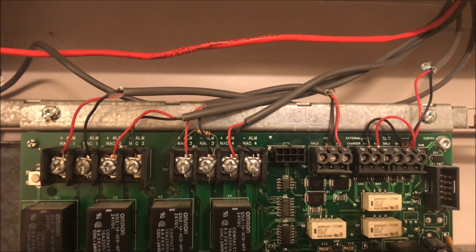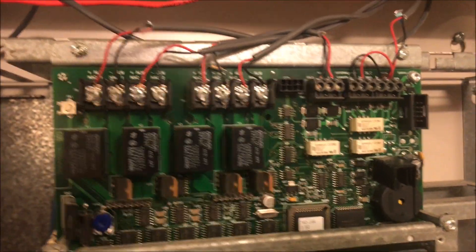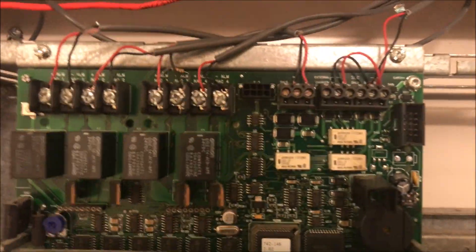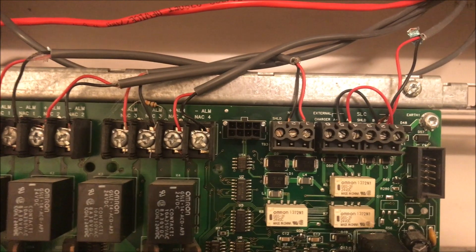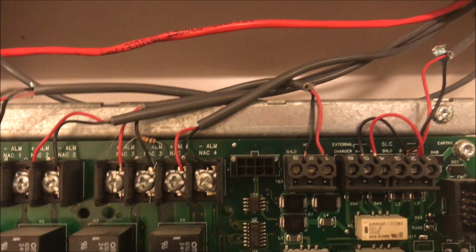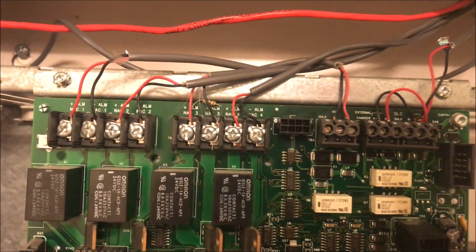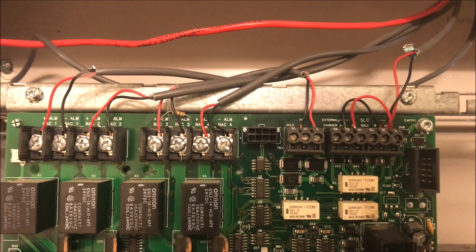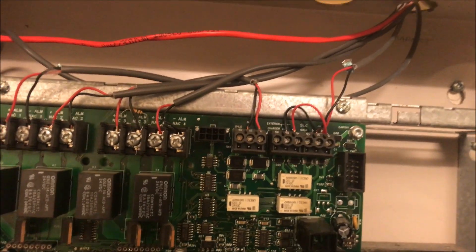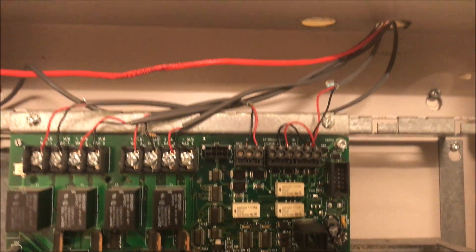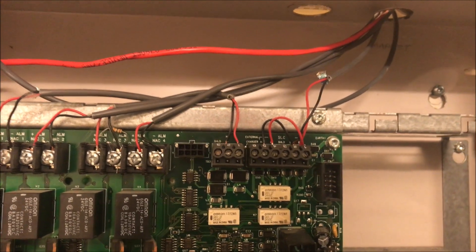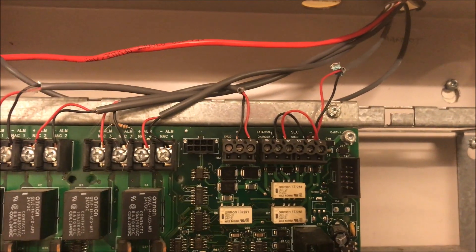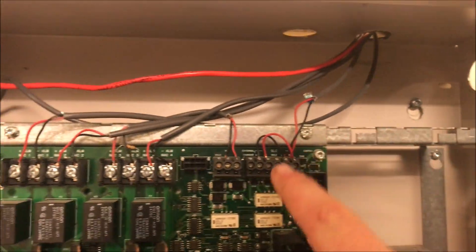Next, this is your IDnet channel. You can have this set up as Class A or Class B. I have mine set up as Class B, which is why there's two jumpers going across for supervision. It's a lot easier instead of running a wire to the end-of-line device. The way I set up mine, I T-tap instead of daisy chaining, so I don't technically have an end-of-line device. I just have a bunch of devices coming off the same wire, so I set it up as Class B, which you can find in the manual.